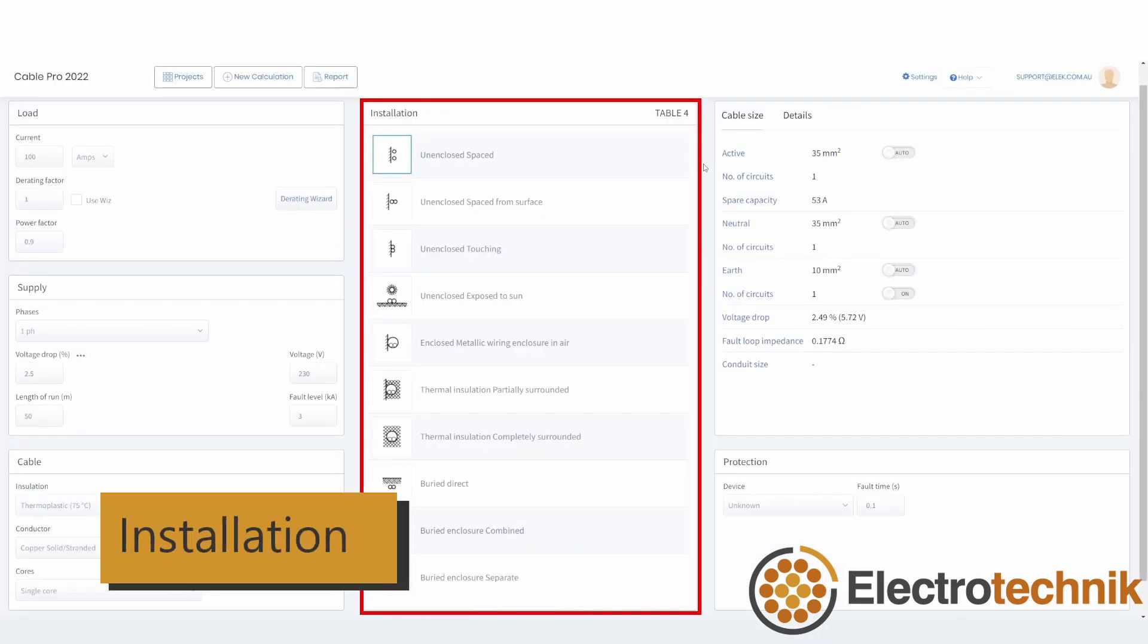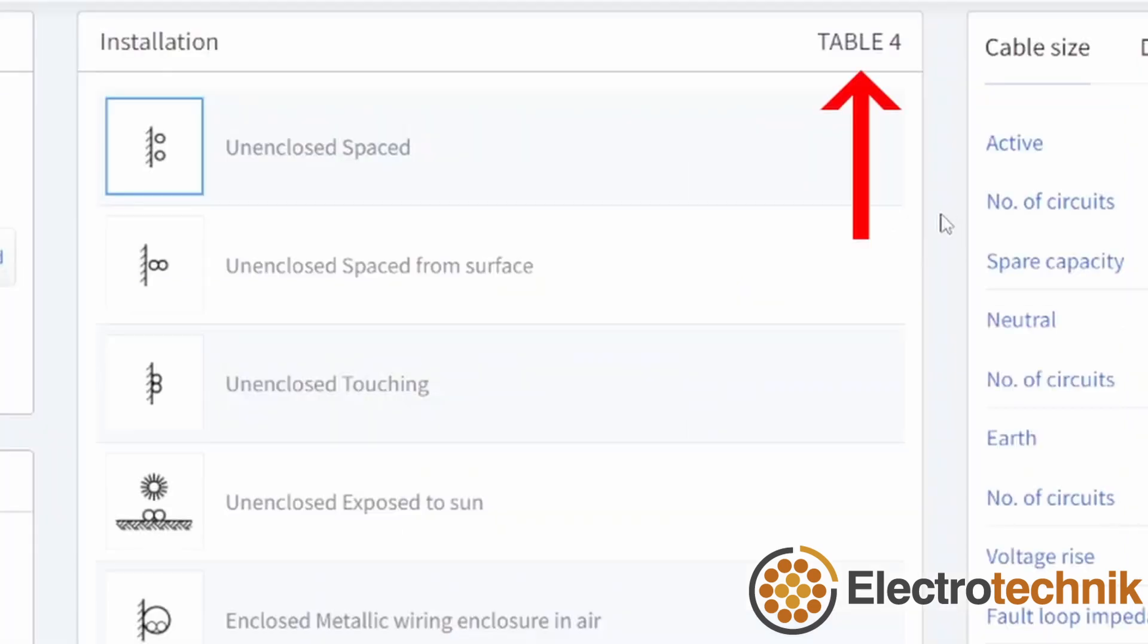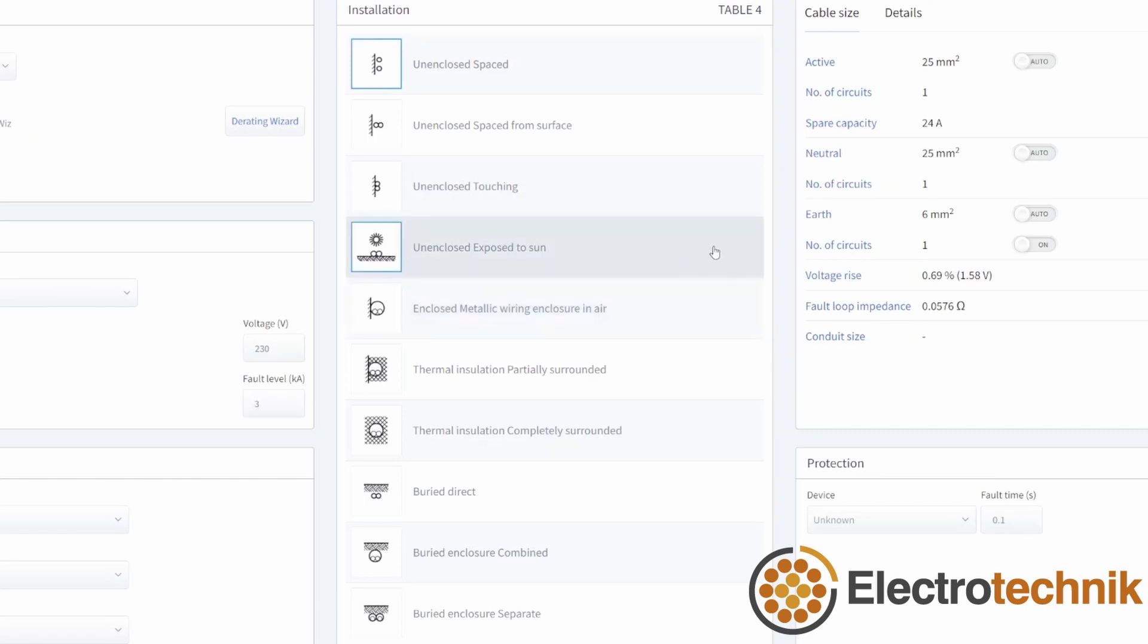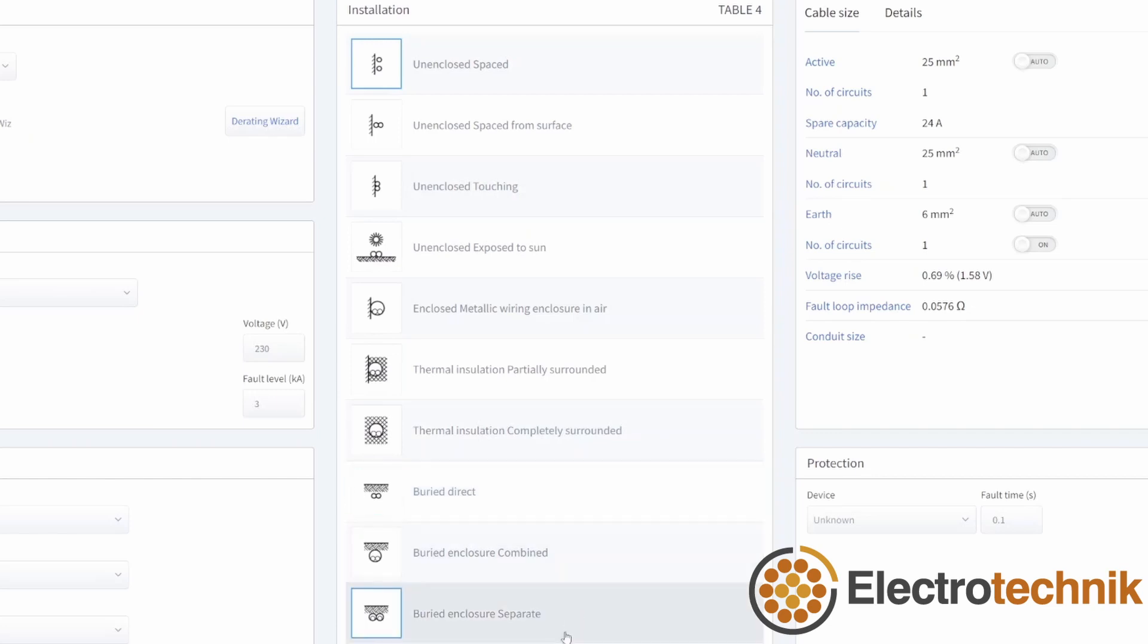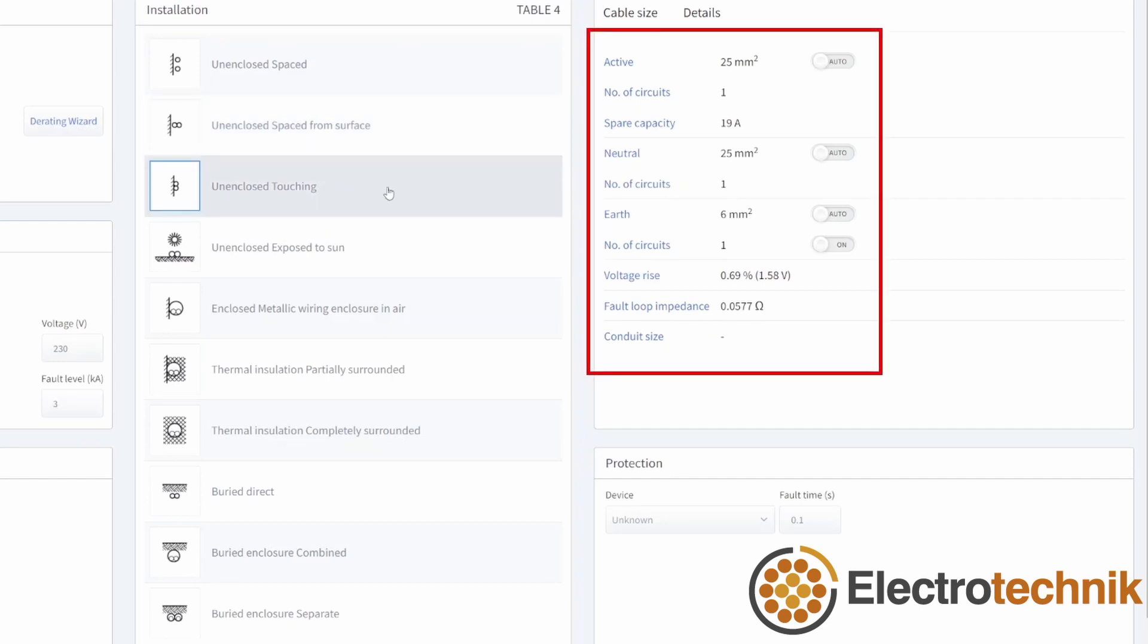The available installation methods are displayed in the centre of the screen. The table number from the standard and from which the installation methods are taken is displayed for reference. Most inputs allow cables to be installed in air, unenclosed or enclosed, exposed to sun, surrounded by thermal insulation, buried direct or buried in ducts. Whenever the installation method is changed or any input is changed, then the cable size results are instantly updated here in the results section.